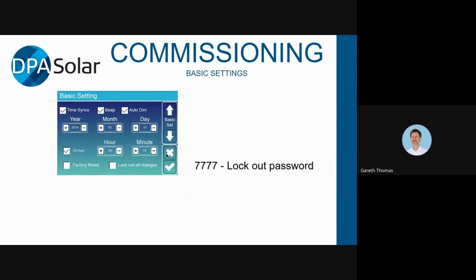So if we go to basic settings, this is where you're going to set up the time of the inverter. The rest of the stuff doesn't matter too much, but the really important one on here is lock out all changes. If you have that on, then every time you need to make a change, you need to come and turn that off. And the default password for that is 4 sevens. The one I have in the office here doesn't have that on. And when I went to help somebody do commissioning on one recently, it was on. And we had to go and turn it off every 30 seconds.